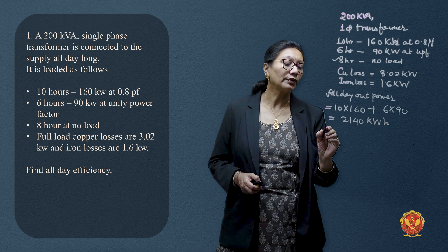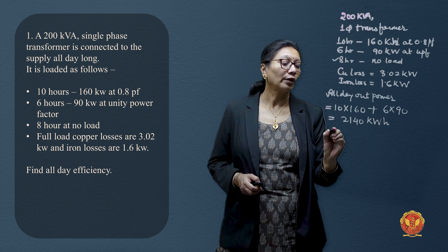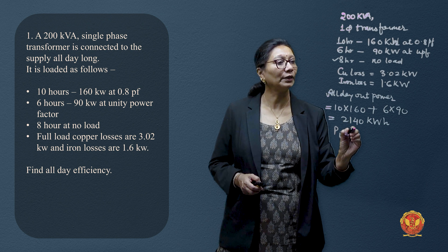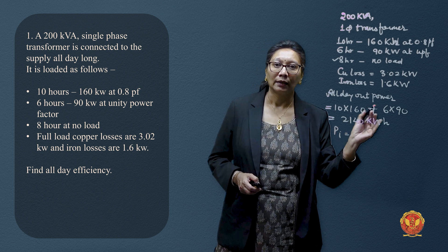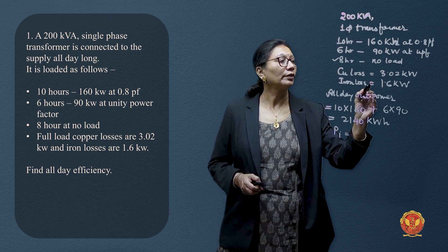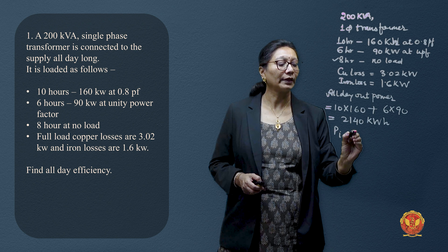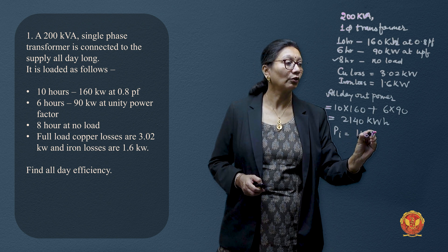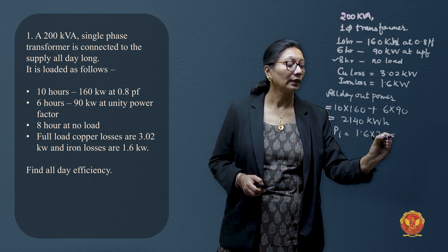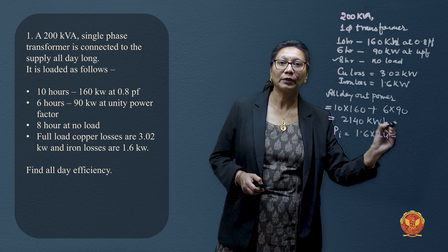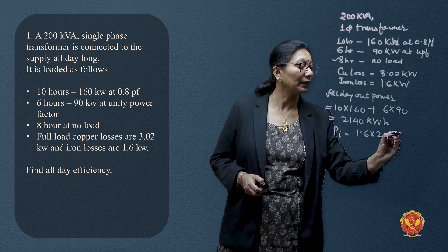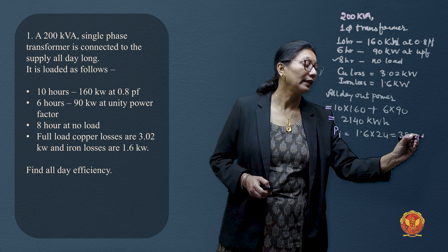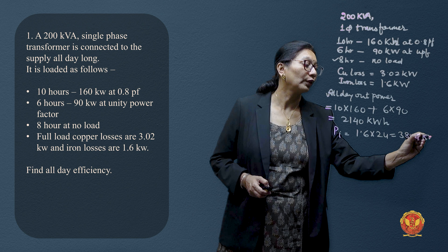Iron losses for 24 hours: since iron losses are constant, we multiply 1.6 kW by 24 hours. This gives us 38.4 kWh for iron losses over the full day.